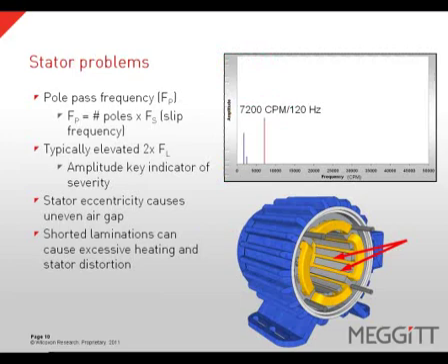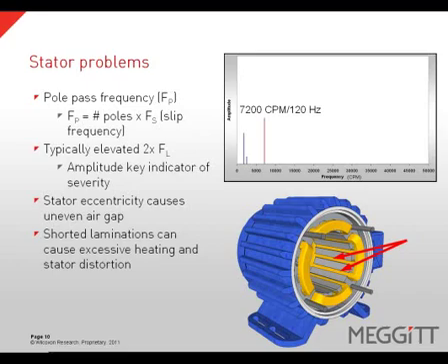Stator problems can manifest themselves in the vibration spectrum in several ways. The presence of pole pass frequency — which is the number of stator poles times the slip frequency — can indicate a problem with the stator. When a problem exists with the stator, there will typically be elevated levels of two-times line frequency, and the amplitude of this frequency can be a key indicator of severity. When a stator is eccentric, it will cause an uneven air gap, elevated levels of two-times line frequency, and hot spots on the stator. Shorted laminations can cause excessive heating and, ultimately, stator distortion.